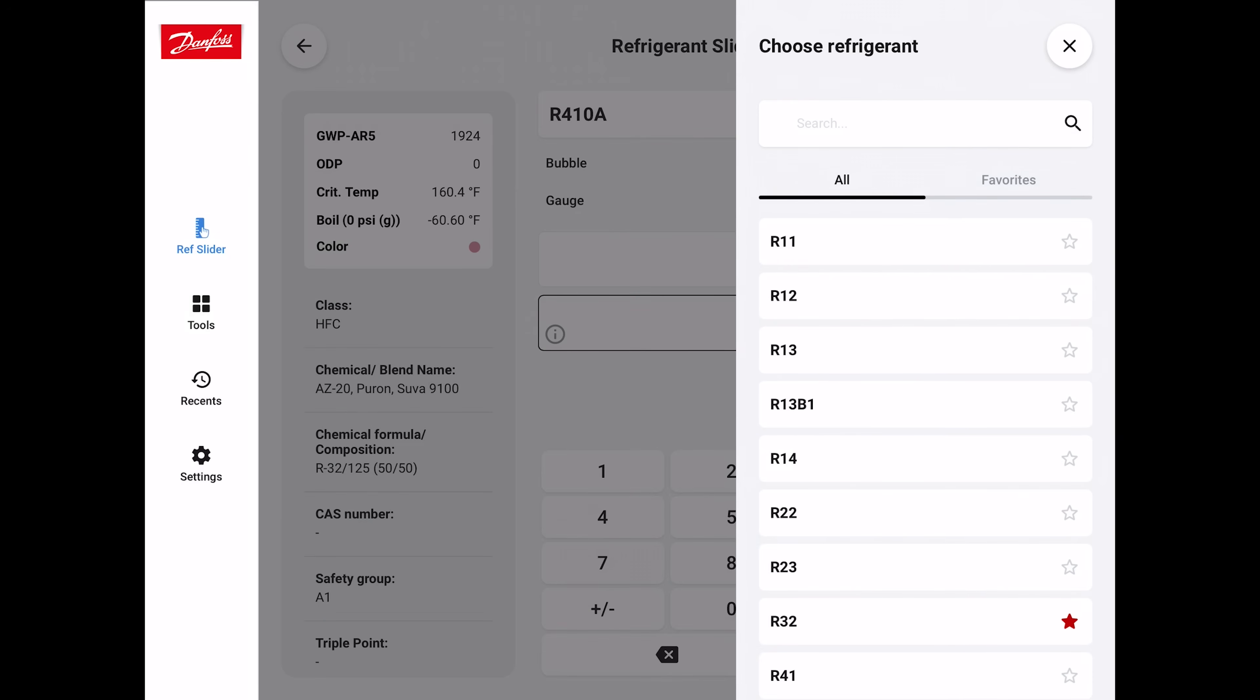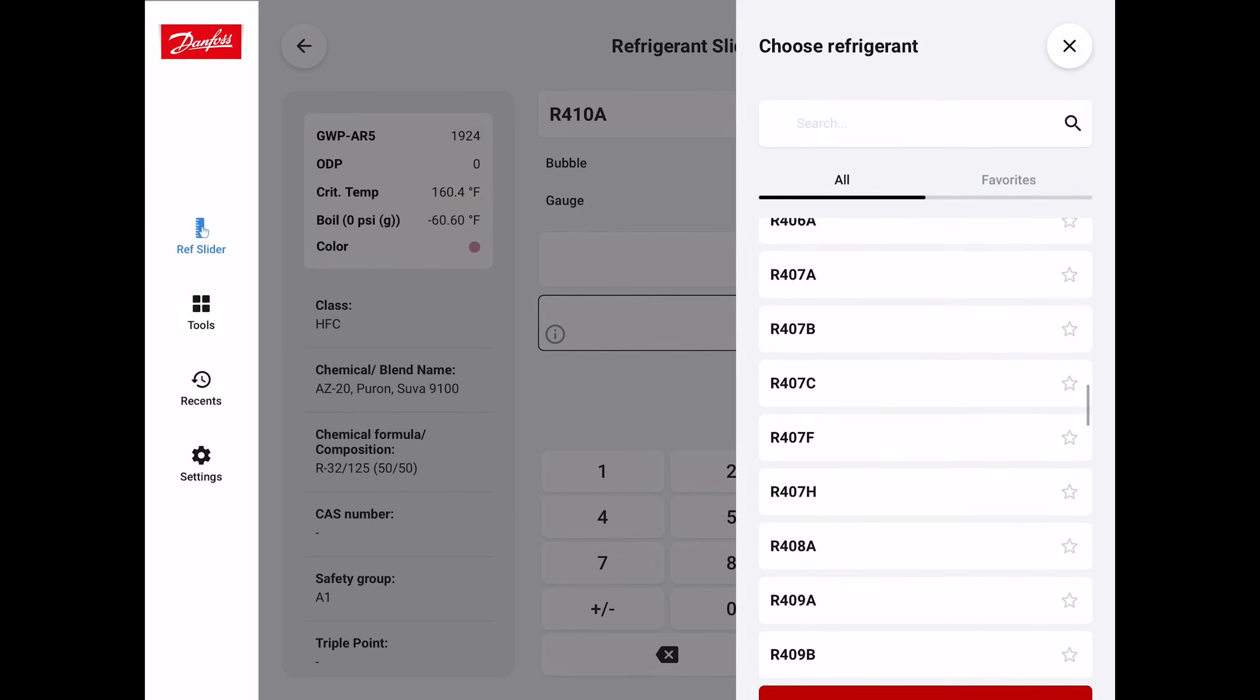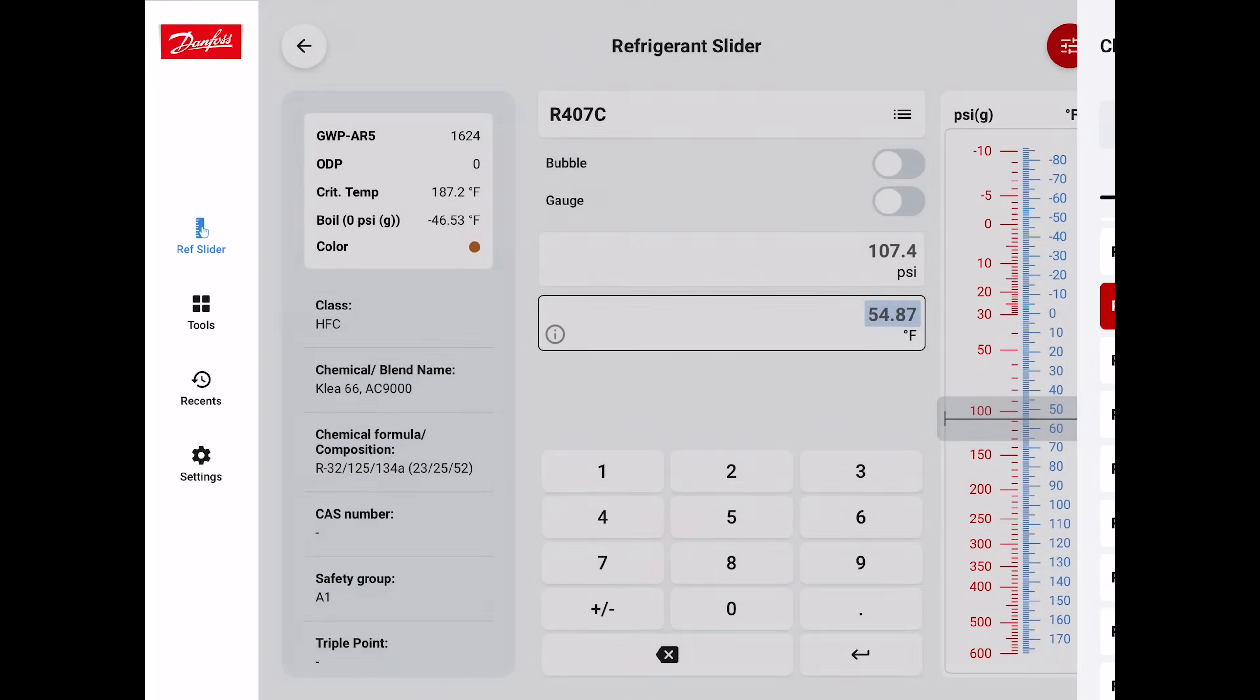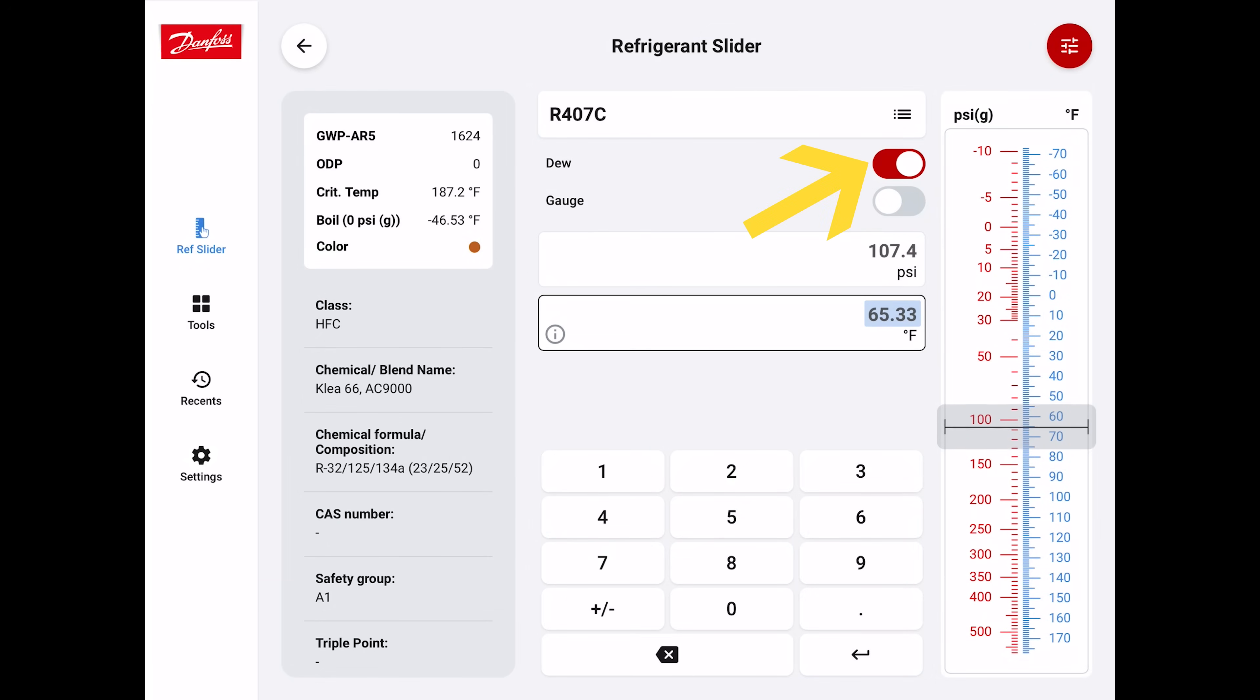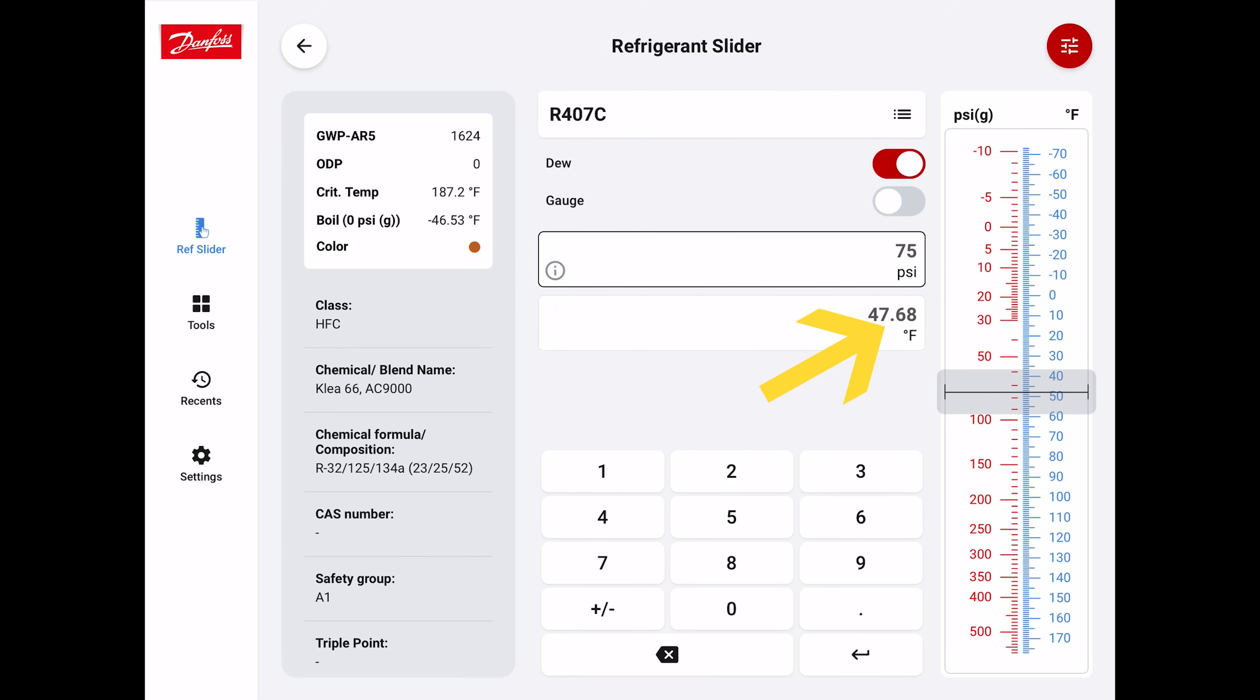Let's look at another refrigerant, R407C. You can also select your favorite refrigerants in here and have them pop up at the top. Right now we're doing bubble. Let's change that to dew. If we have a 40 degree evaporator coil, that's showing you that the pressure would be 63 PSIG. If the pressure was 75 PSI, we see a temperature in the middle of the evaporator coil of 47.68.